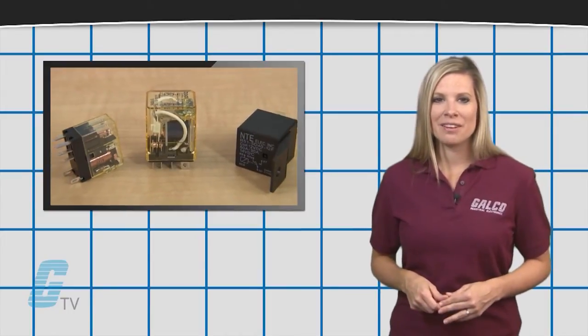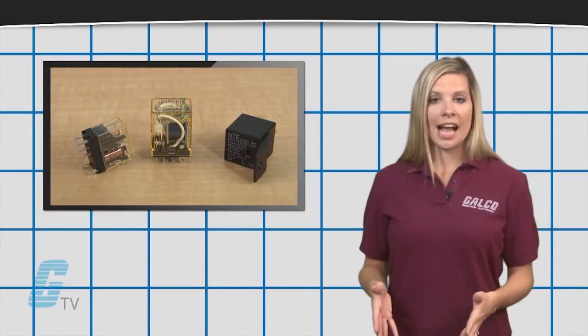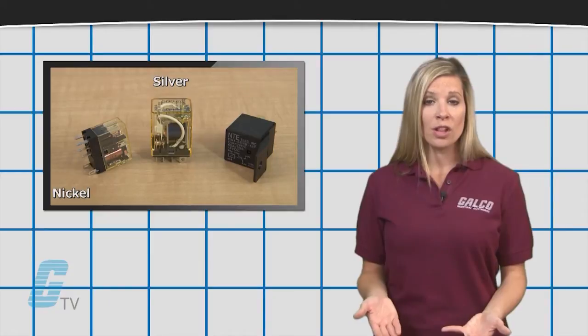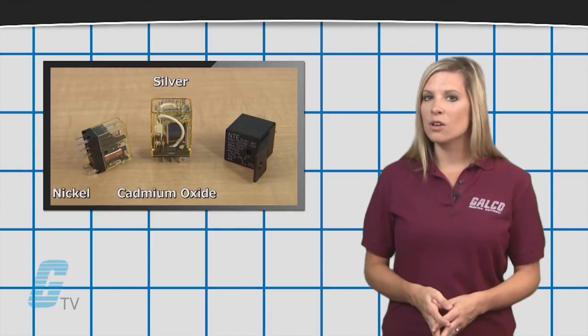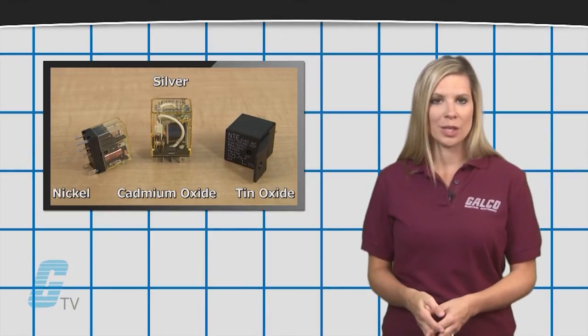For applications between 5 to 30 amps, relay contacts made of silver nickel, silver cadmium oxide, or silver tin oxide are widely used.